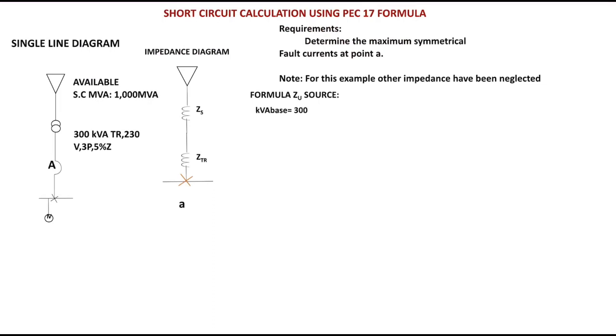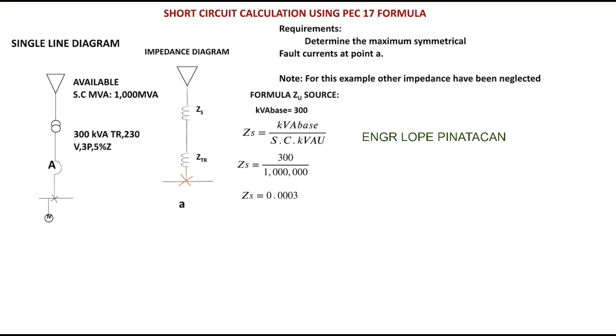And then we have the kVA base equals to 300, and then the formula is the kVA base divided by the short circuit capacity of the utility kVA. And then we will replace the formula with the given values. So kVA base is 300 divided by the short circuit capacity of the utility. We multiply the 1000 MVA by 1000 because we are using kVA, so we have 1,000,000 kVA short circuit. And then the result is the impedance at the source is 0.0003. So we have now the value of the impedance at the source.